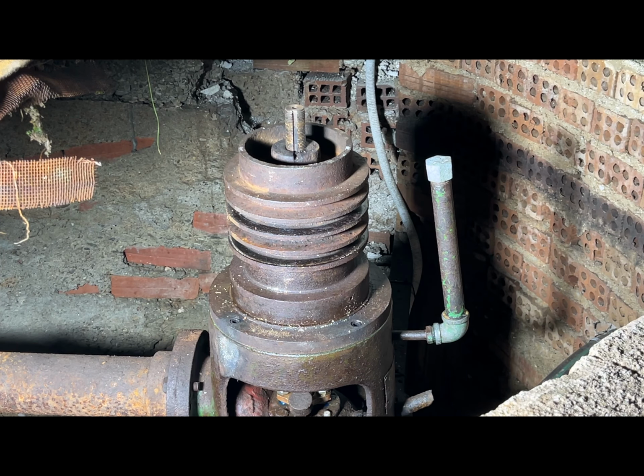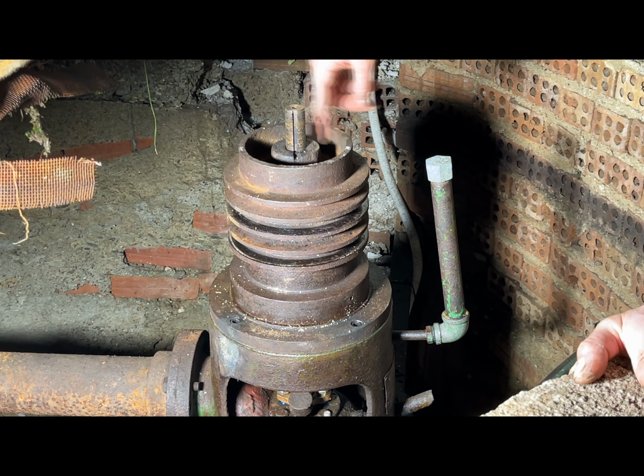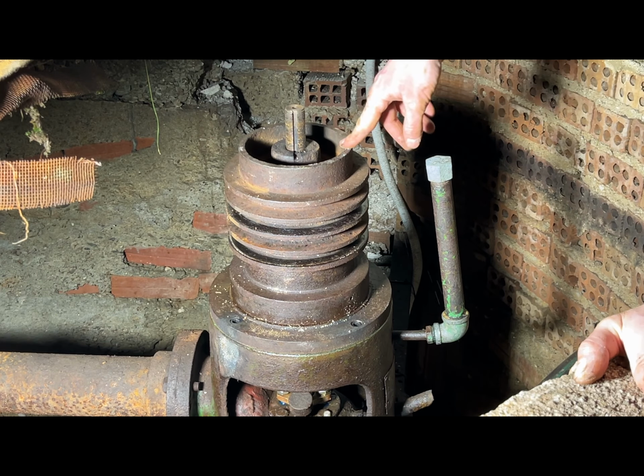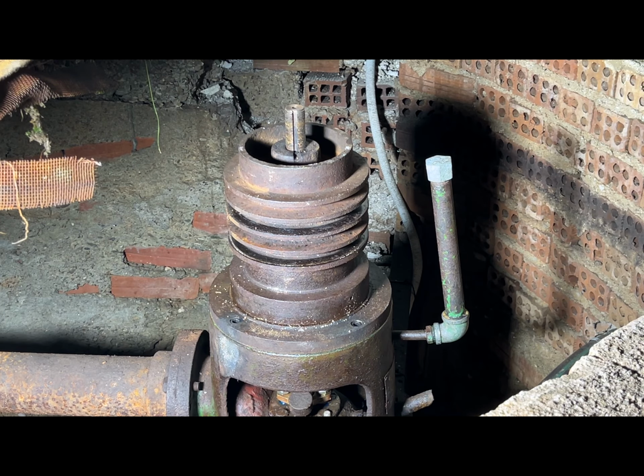You're going to tighten the nut down until it starts spinning, and then take your manufacturer's adjustment, which in this case is around 4 to 5 turns after it starts spinning, and then you're done. You should also take into account the type of impellers you have, open type, closed type, and so on, because in some it doesn't really matter how you adjust it.